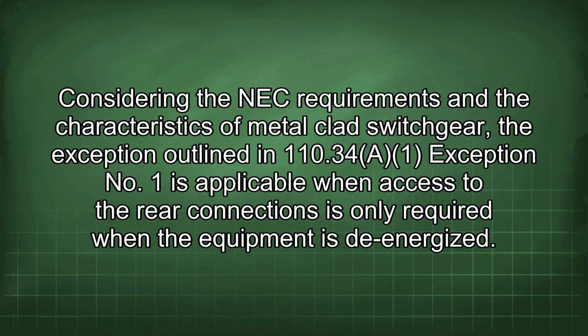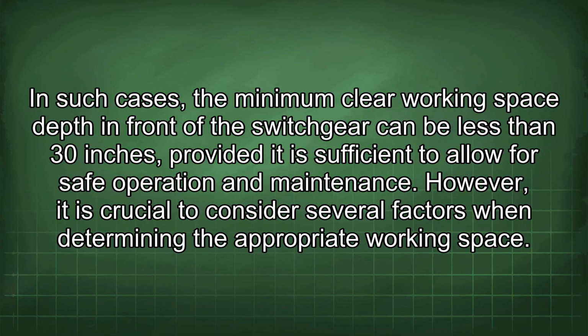Considering the NEC requirements and the characteristics of metal-clad switchgear, the exception outlined in 110.34(A), Exception No. 1, is applicable when access to the rear connections is only required when the equipment is de-energized. In such cases, the minimum clear working space depth in front of the switchgear can be less than 30 inches, provided it is sufficient to allow for safe operation and maintenance.